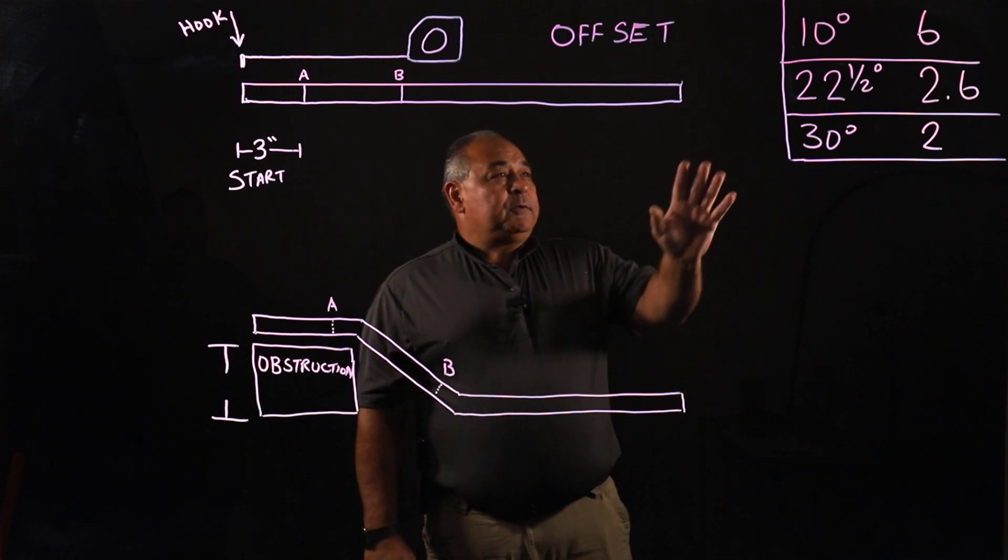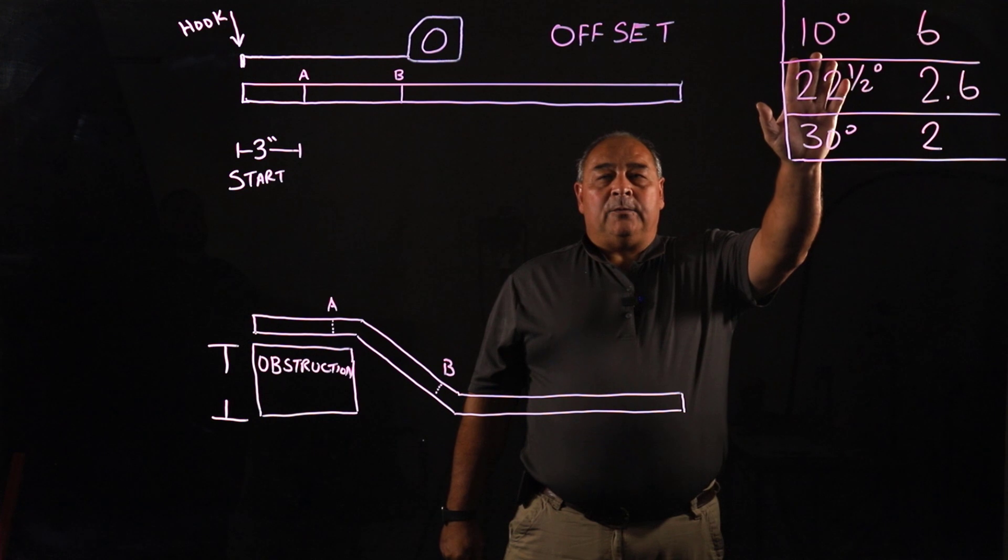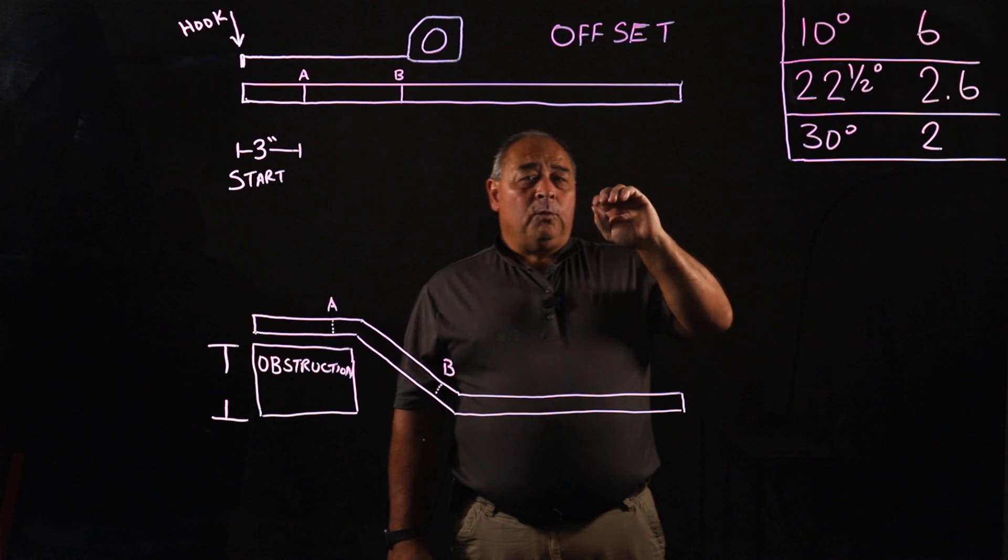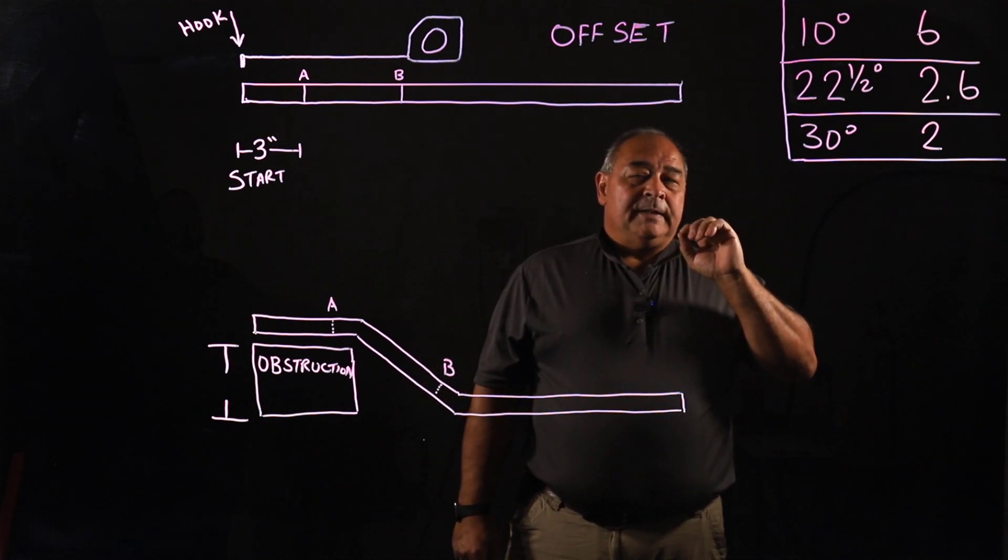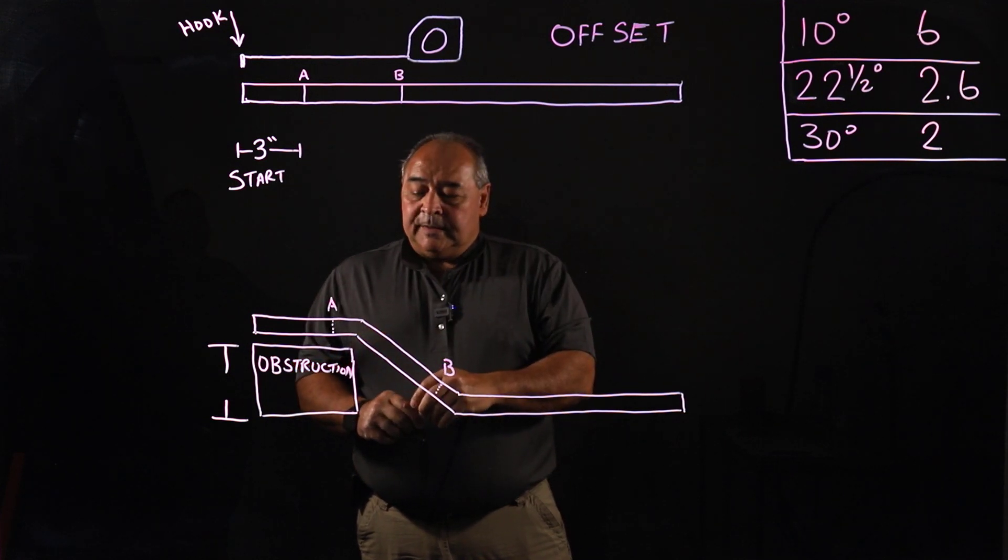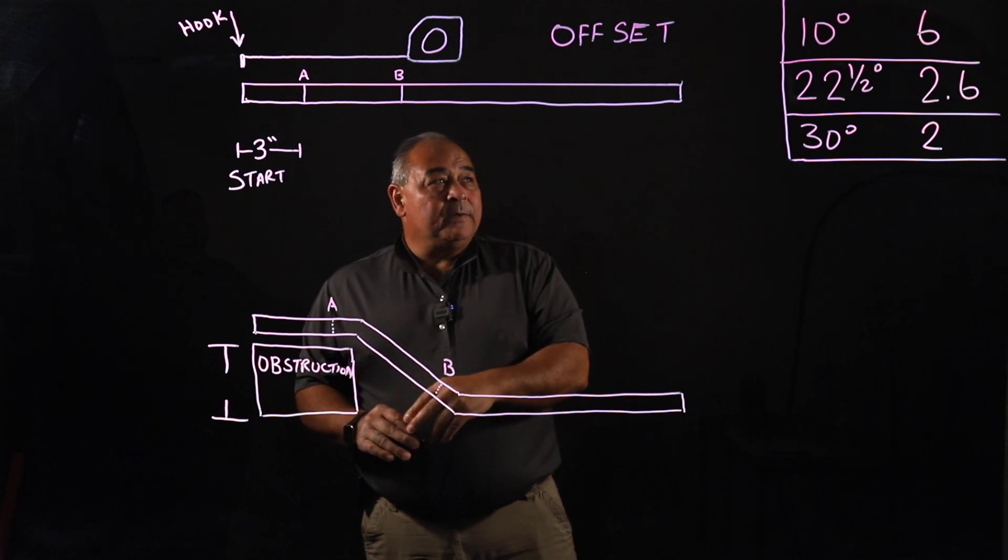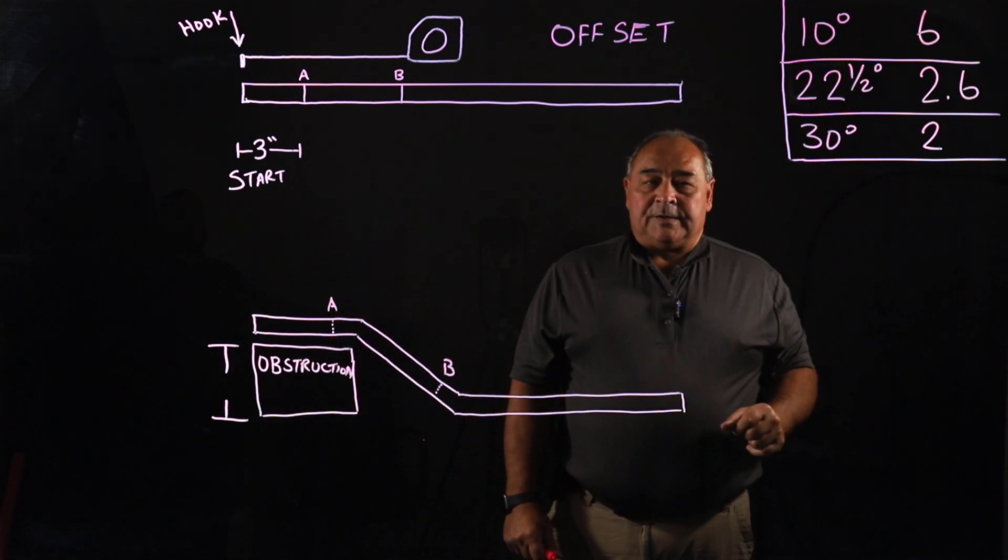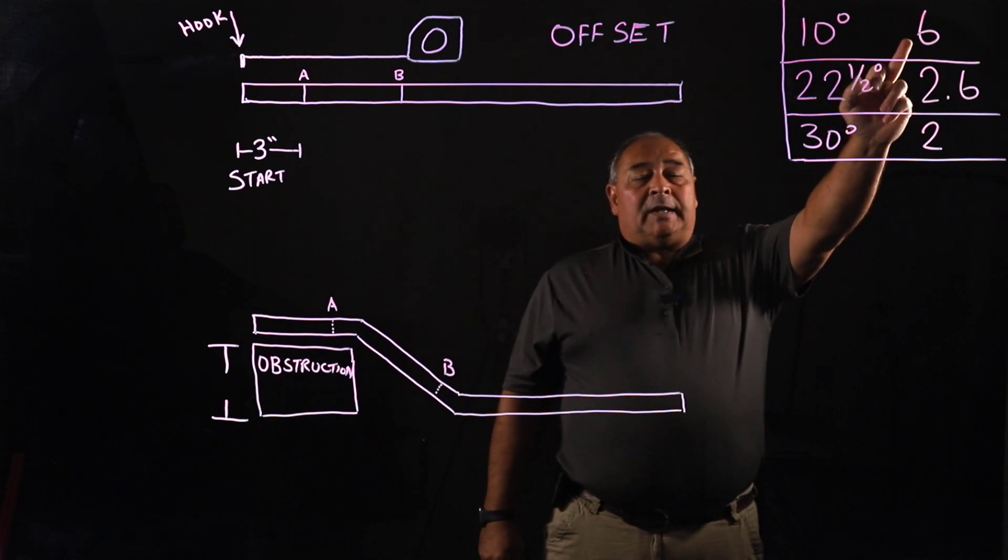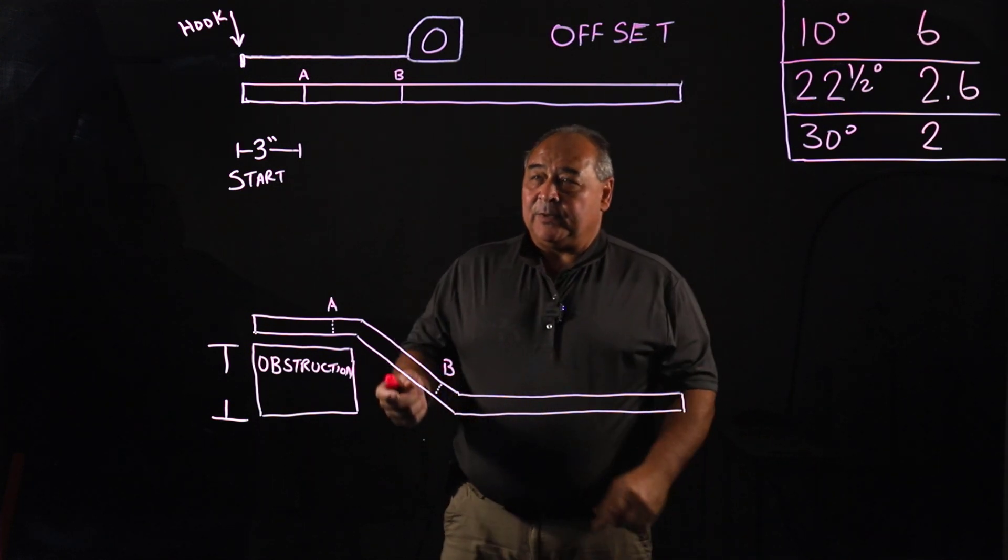Why is that? If you look over here, we've got this grid over here that talks about what our multipliers are. Our multipliers is what we multiply our measurement of our obstruction by. Like if this obstruction, let's say it was five inches. If it was five inches and we were going to use 10 degree offsets or 10 degree bends to make an offset, we would multiply five inches times six.